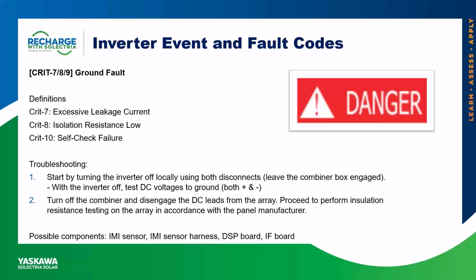As mentioned with CRIT 8, the inverter can indicate which pole is detecting low insulation resistance, but this is a calculated value. There is not a component inside of the inverters that is injecting anything back onto the array. In terms of possible components within the inverter that could be in question, I have listed here the IMI sensor, the IMI sensor harness, the DSP board, or the interface board.